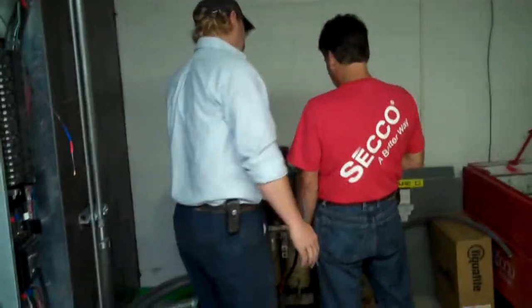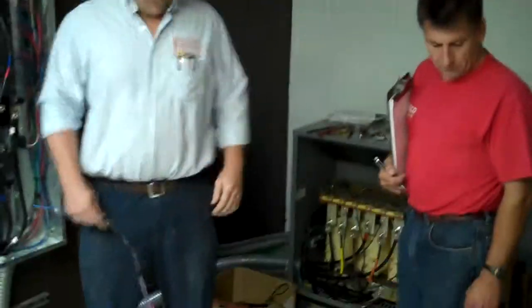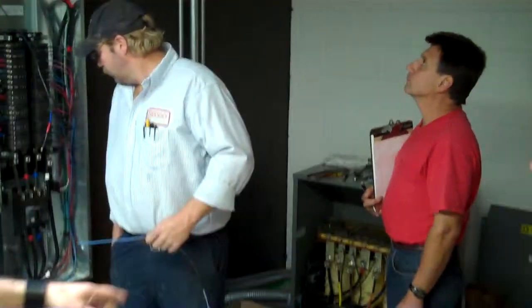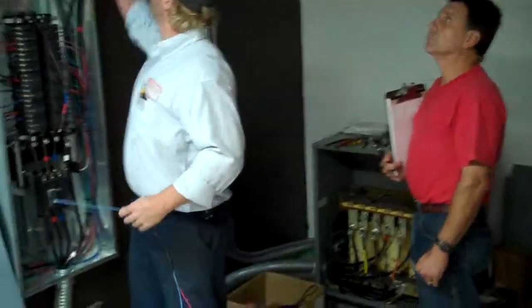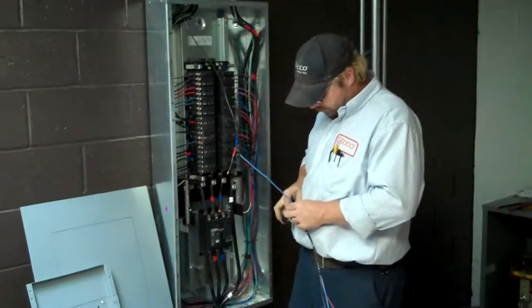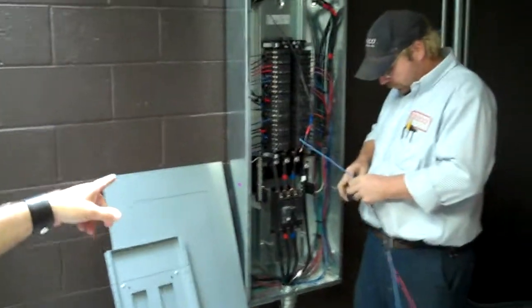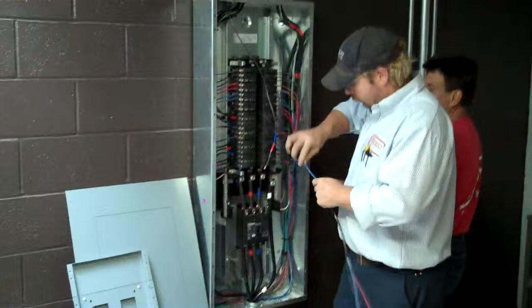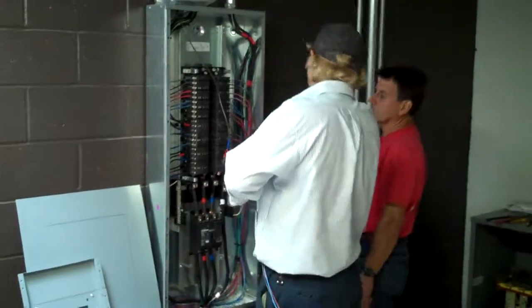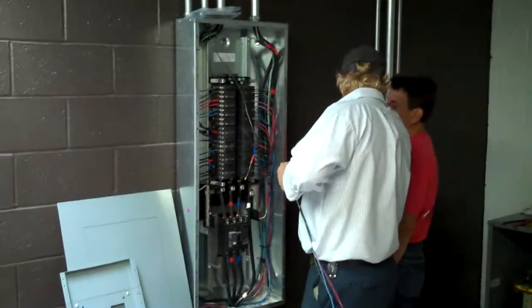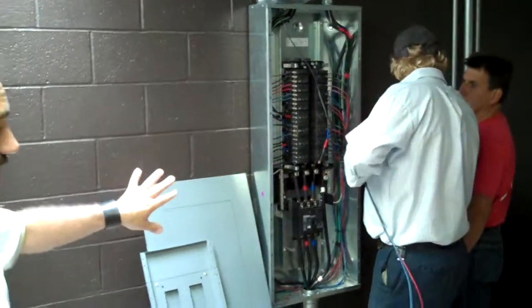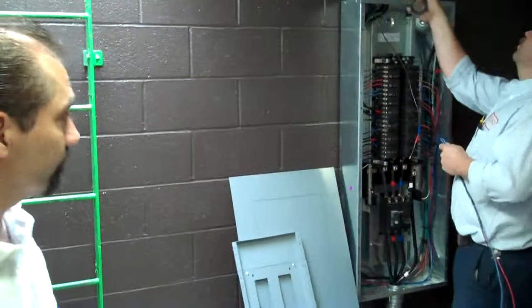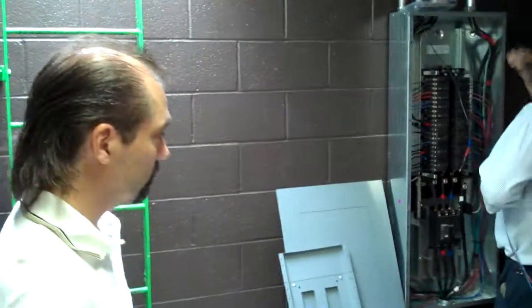Awesome. And so what do we have here? We have a transformer, and this is the electrical connection for tying into the facility. What we actually did is we came from the main service located down in the basement, set a separate transformer up here, and a brand new panel that's dedicated solely for all the equipment on the roof. Now this panel here will have all the Eco condensing units on, and all the new Renew Air energy recovery systems on. So this panel is solely dedicated for that purpose. Great. Awesome. Well, let's take a look at the classrooms then.